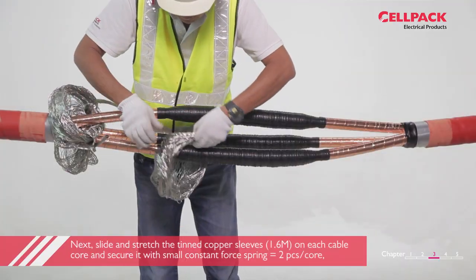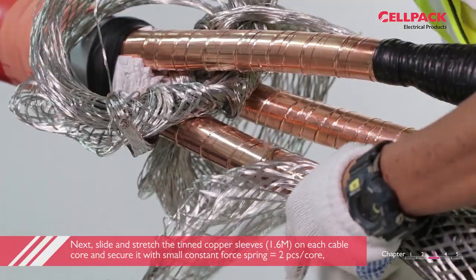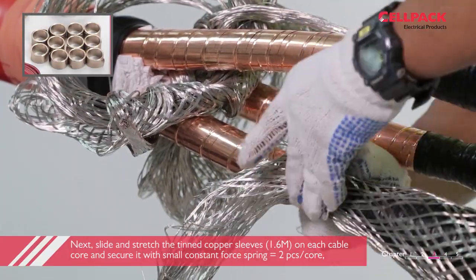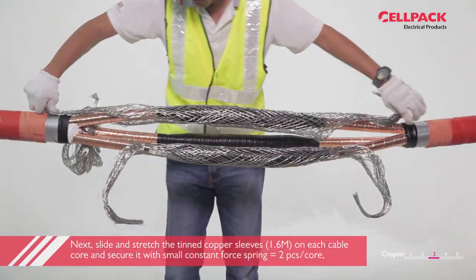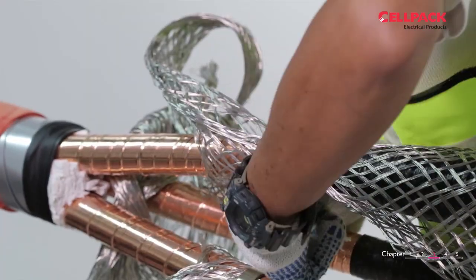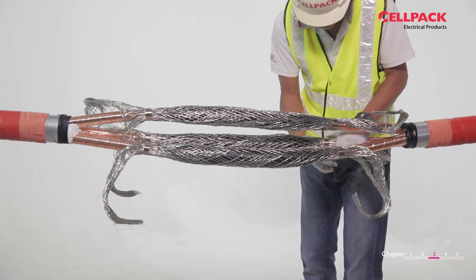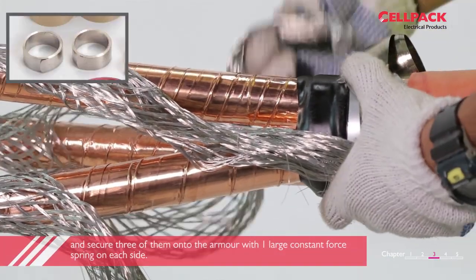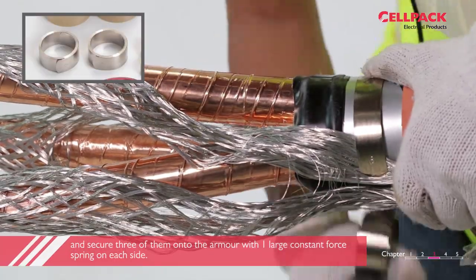Next, slide and stretch the tinned copper sleeves on each cable core and secure it with a small constant force spring — two pieces per core. And secure three of them onto the armour with one large constant force spring on each side.